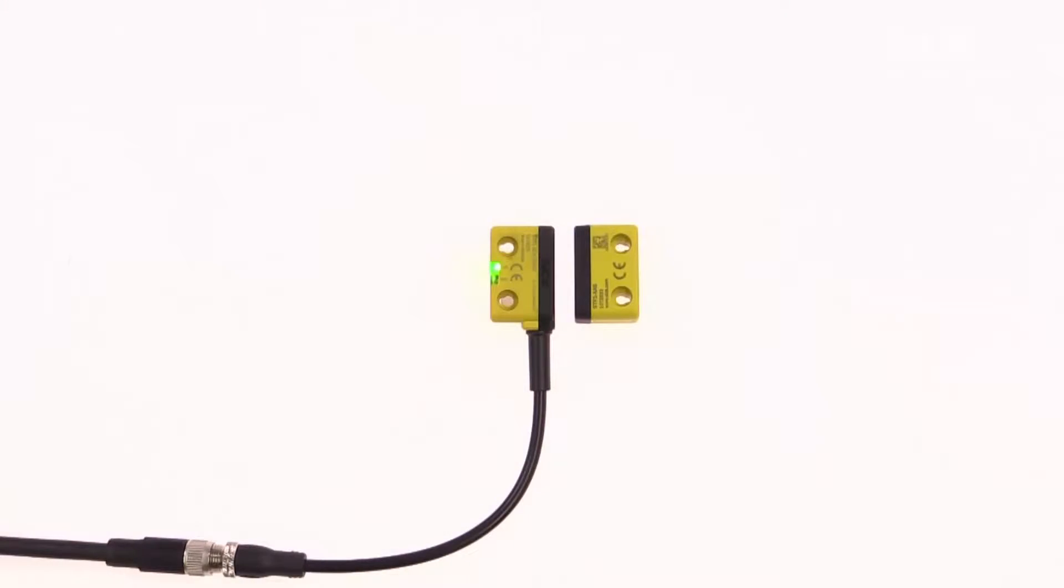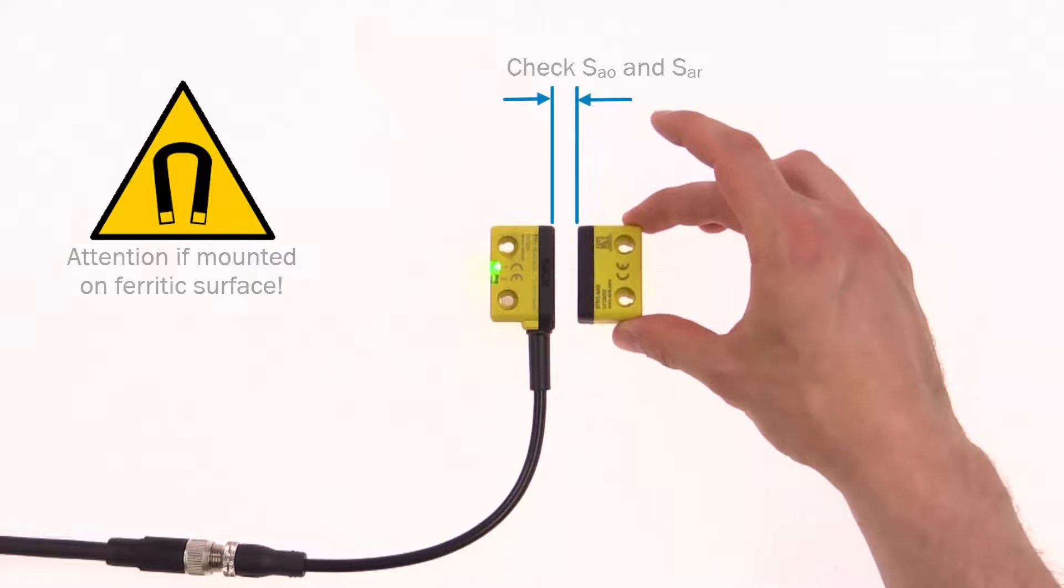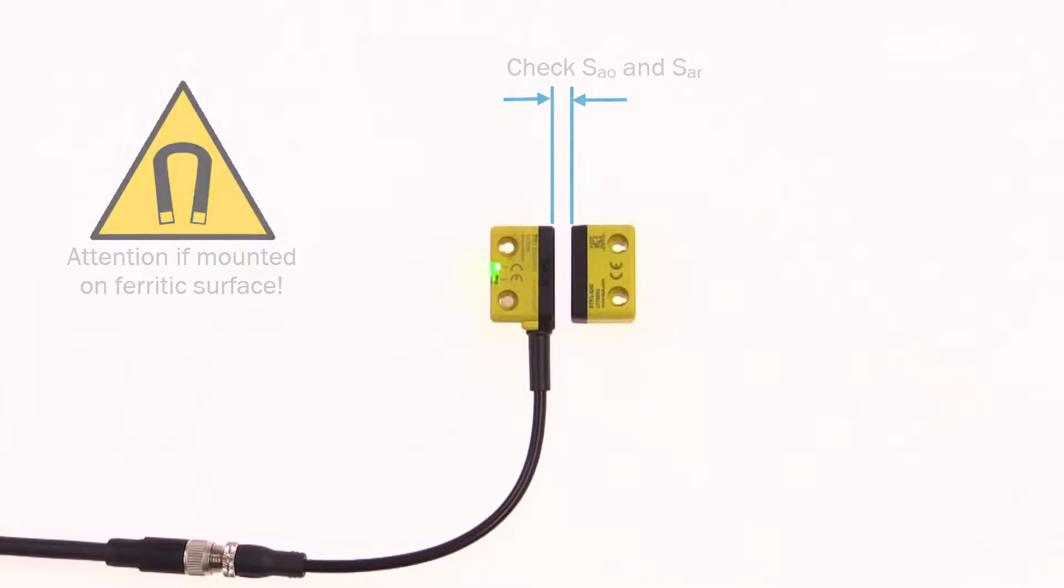The STR1 should be mounted on a non-ferritic surface. If that cannot be assured, the operating range may be affected and the switching distance must be verified before use.